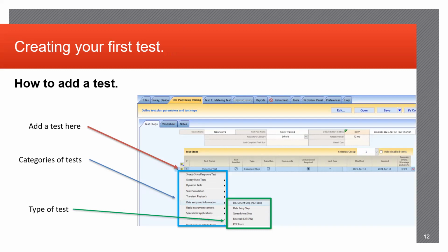So, setting up your first test plan, as shown here in the software, you start a new test. You have a drop box here of different types of tests that you may want to implement. Some of these tests can be identified based on what element you're going to be testing from the relay settings. Steady state tests will have linear pickups, testing your zones of protection, your Mho circles, et cetera. State simulation tests as well. That's for testing the relay logic when you can't identify an element you want to pick up, but you're more or less testing the internal logic of the relay, as well as any output or input contacts that you may want to prove as well.